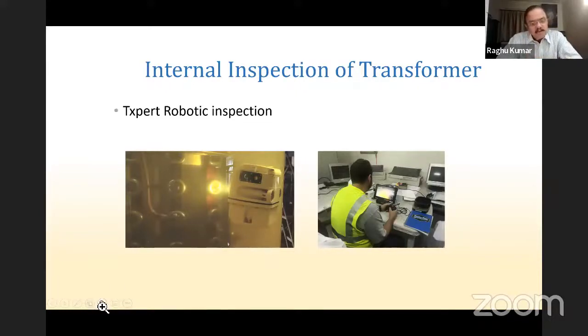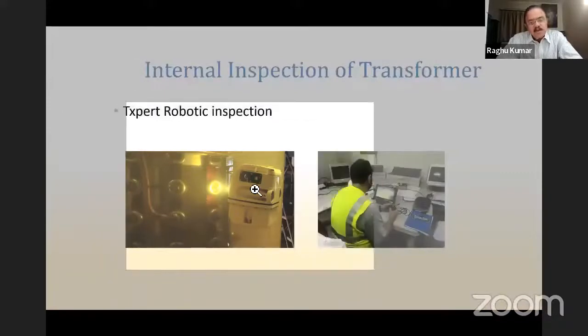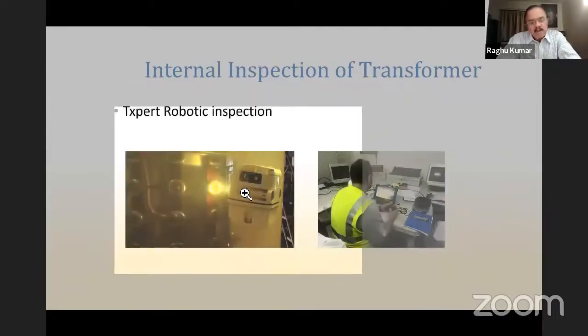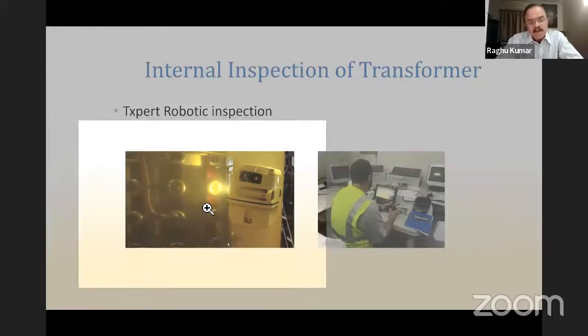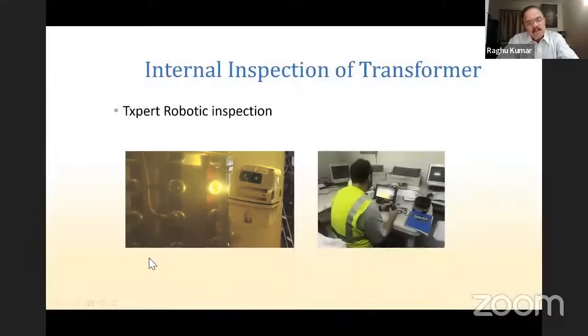And what this is seeing is here. See, this is a robot going on an internal inspection. This photo is taken from his display. And these are tap changer contacts. It goes near each and every contact and checks every contact for loose connections or flashover marks or anything. Like this, it can go over the complete transformer and exactly pinpoint what the issue is. Then it becomes much easier to award a new contract, or the scope can be very clearly described.